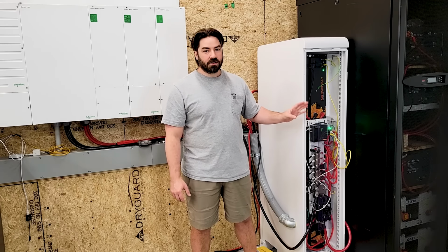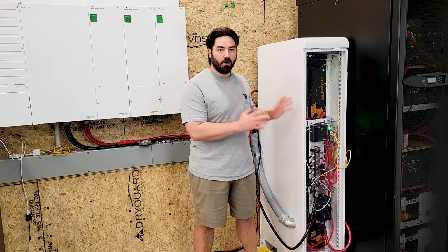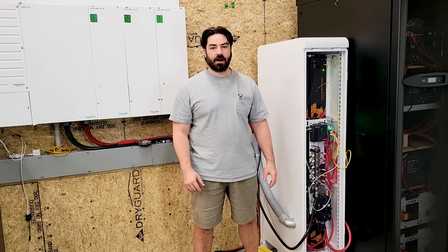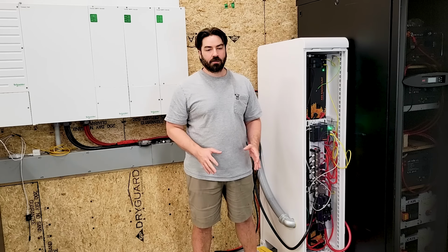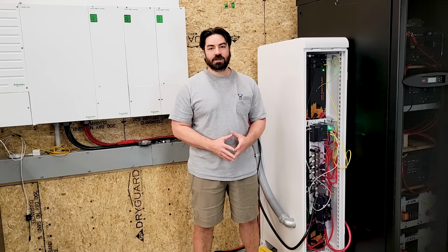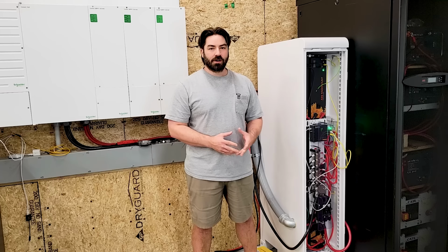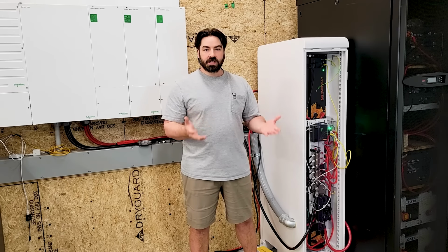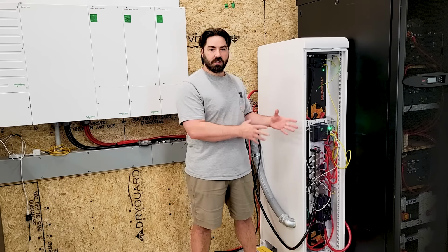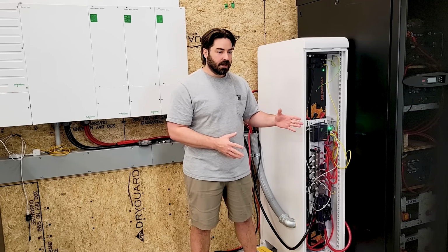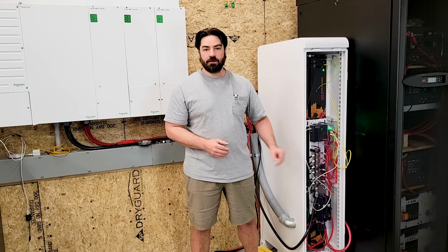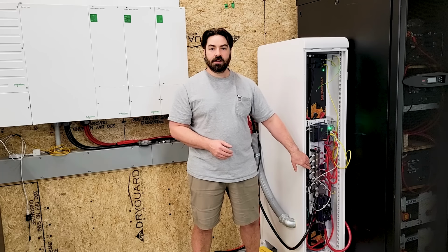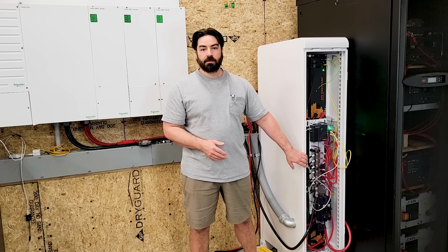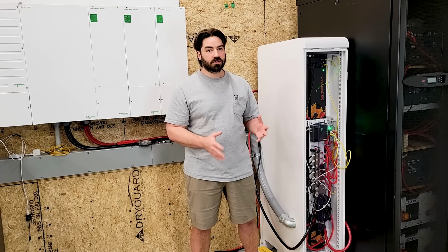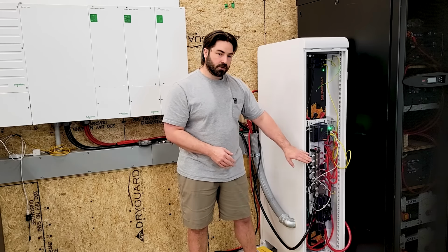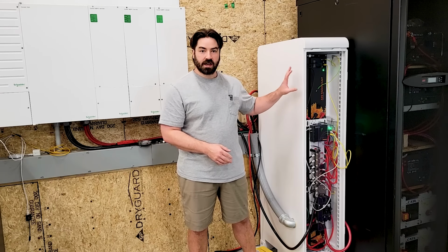Now the bus bars, the wires, the batteries, we know those things can absolutely handle 500 amps continuous without any trouble. But paralleling those two separate circuit breakers will maybe trip you up. So I would suggest that if you're in a situation where you know you're going to need 500 amps on a regular basis, then maybe go with the Class T fuses in there instead, and then you can up those a little bit, maybe a pair of 300 amp Class T fuses or something along those lines in order to pull the full amperage out of this cabinet.